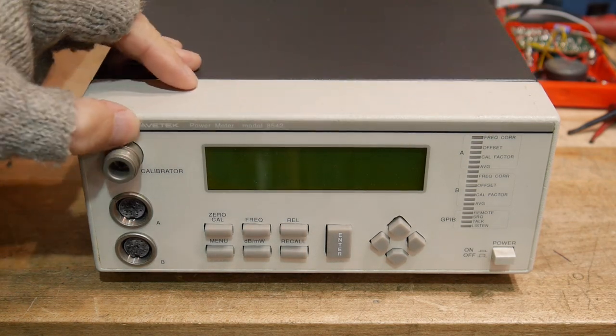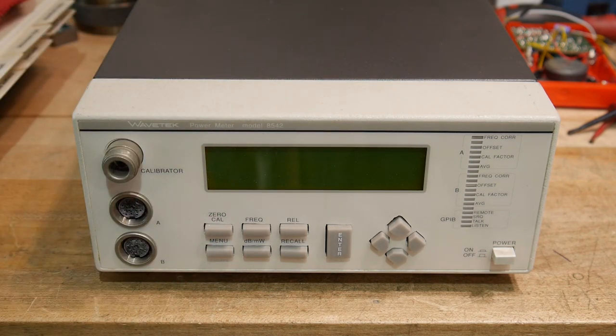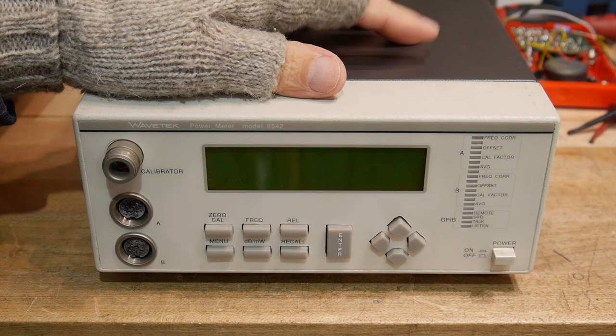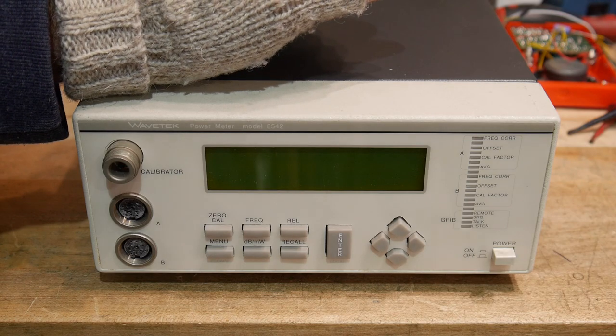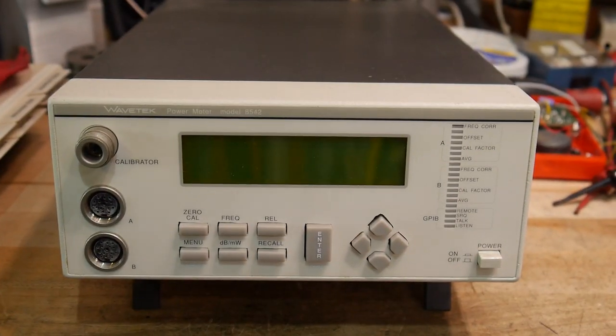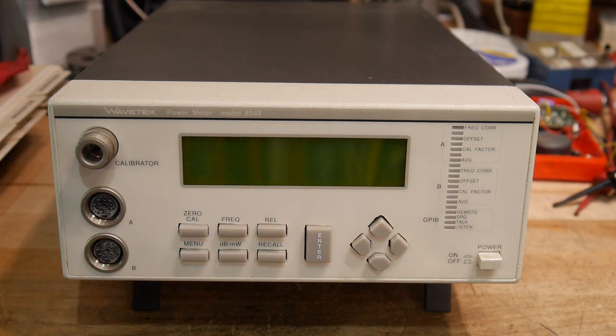This is a microwave power meter by the Wavetek company. I worked at Wavetek as a principal engineer and then got promoted to R&D manager, and this is one of the products I designed. I was responsible for every bit of this instrument from the front panel to the power connector. It is a two-channel power meter, and you can use various sensors — we had a whole product line from 1 MHz to 40 GHz, with different power levels and built-in attenuators.